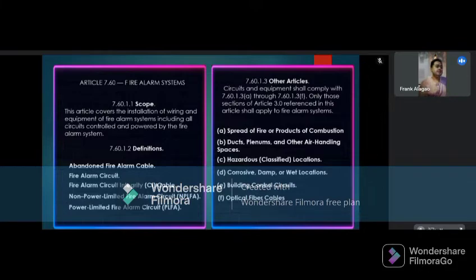So, Article 7.60, Scope. This article covers the installation of wiring and equipment of fire alarm system, including all circuits controlled and powered by fire alarm system. So, definitions. Number one is yung abandoned fire alarm cable. So installed fire alarm cable that is not terminated at equipment other than connector and not identified for future use with a tag. So next yung fire alarm circuit.